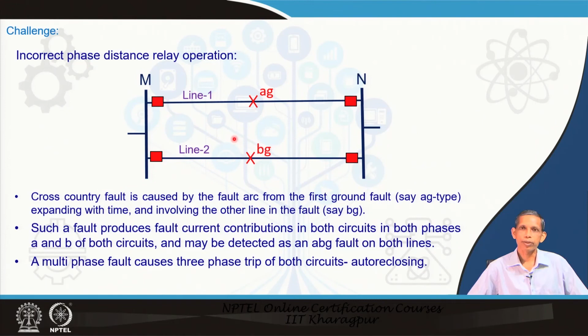Now, we discuss the issues on the compensation factor, the zero sequence compensation factor contributed by the other line, the other circuit. We discussed mostly zone 1, but in many aspects the zone 2 impedance setting is not taken care of in general, because the zone 2 setting is extended to either 120% to 150% of the line being protected. That larger value takes care of the whole line of zone 1 with sufficient safety margin. So, zone 2 may not be in trouble. Zone 3, however, is a backup protection for the subsequent line from the remote bus.